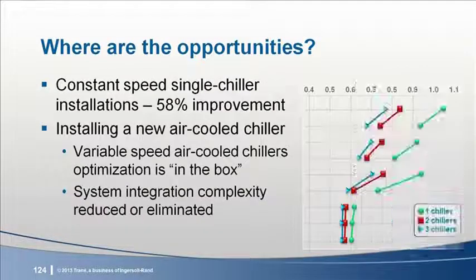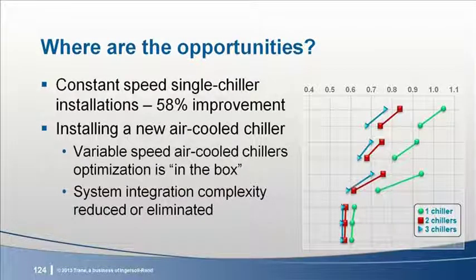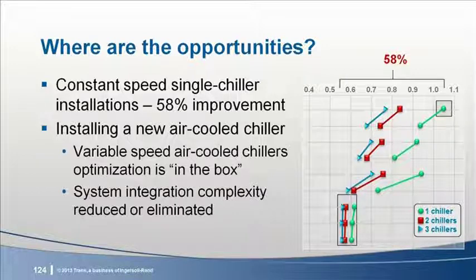And don't overlook the potential in constant speed single chiller installations. The ancillary power quickly dwarfs chiller power in these systems at part load, and they experience the drop-off in chiller efficiency more acutely at part load. These two factors combine to create excellent applications for retrofits. Using advanced controls, single chiller installations can have similar performance to multiple chiller plants.